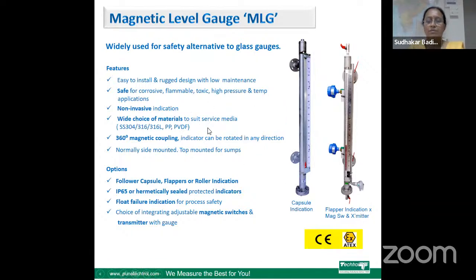The material is available in various options like stainless steel, various stainless steel grades, then PP and PVDF to suit the service media. The float inside the gauge will have 360-degree magnetic coupling. Hence, the indicator can be rotated in any direction as per your requirement. This gauge is normally side mounted. However, a top mounted gauge is also available for underground tanks or sumps.